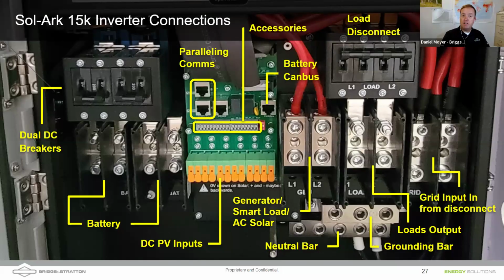We could also have it be a smart load output where we can program the solar that once the batteries get to a certain state of charge, let's say maybe 90%, let's go ahead and turn on that port, power luxury loads like maybe a hot tub. And when the batteries start to drain, maybe below 50%, we can turn this port off. So this can not only be an input from generator or AC coupled solar, but it can also be an output as well. Notice the neutral bar here in that horizontal position.